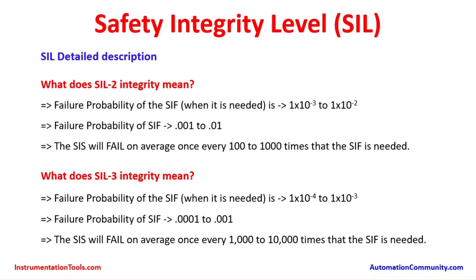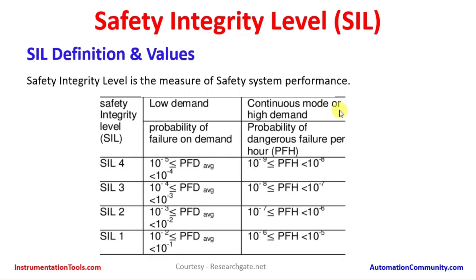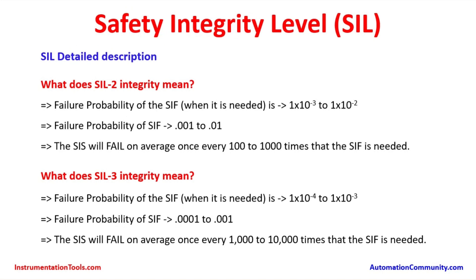For SIL 2 integrity, the probability of failure of the SIF ranges from 1×10⁻³ to 1×10⁻², which is a PFD average equivalent to 0.001 to 0.01. In practical terms, the SIS will fail on average once every 100 to 1000 times when the SIF is needed. That means for every 100 to 1000 demands, there is a probability of failing once — that is SIL 2 integrity.